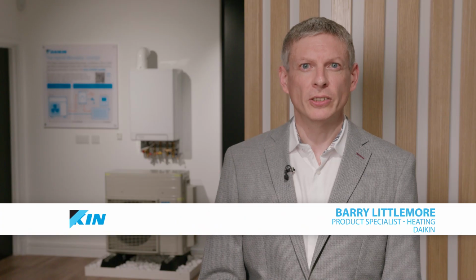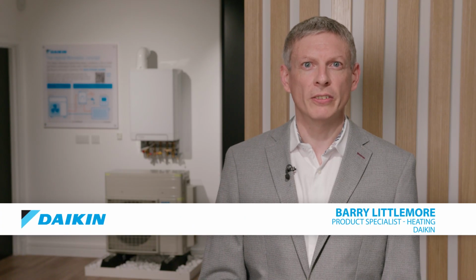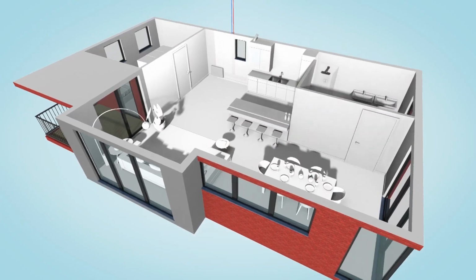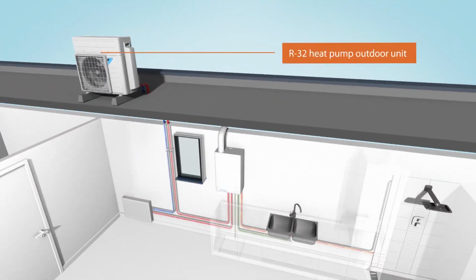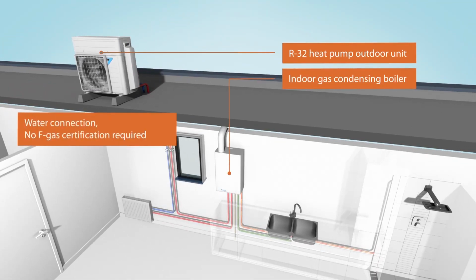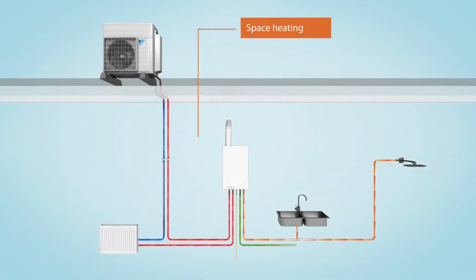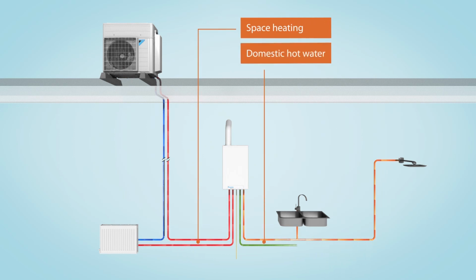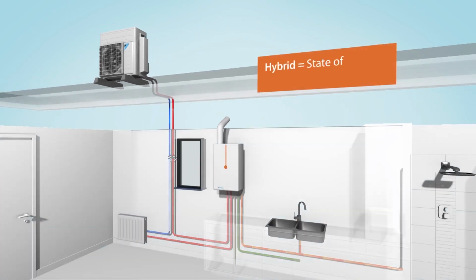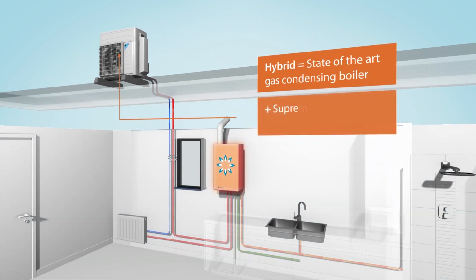The installation layout of the 2 heat sources for the standard hybrid configuration is straightforward. The heat pump and the boiler are plumbed in series, with heated water flowing from the heat pump to the boiler, through the heating system, returning directly to the heat pump. This arrangement allows the heat pump, or the boiler, or both in true hybrid operation to contribute to the space heating of the property. Hot water is supplied directly from the combi boiler.